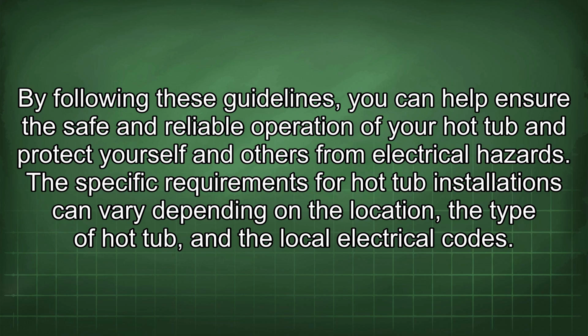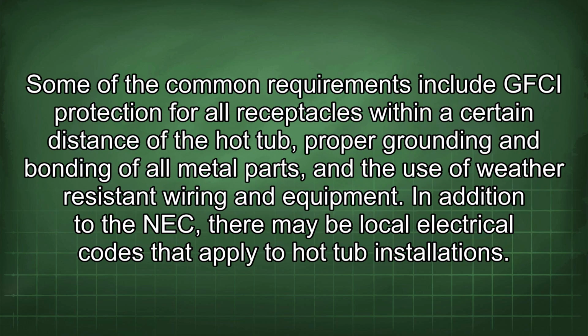The specific requirements for hot tub installations can vary depending on the location, the type of hot tub, and the local electrical codes. Some of the common requirements include GFCI protection for all receptacles within a certain distance of the hot tub, proper grounding and bonding of all metal parts, and the use of weather-resistant wiring and equipment. In addition to the NEC, there may be local electrical codes that apply to hot tub installations.